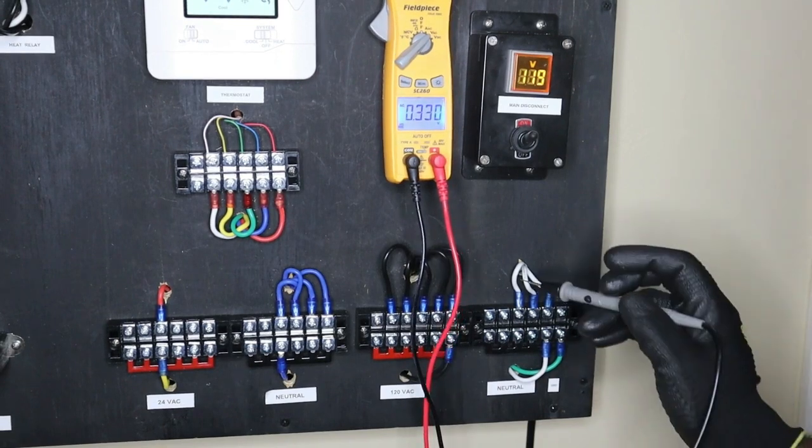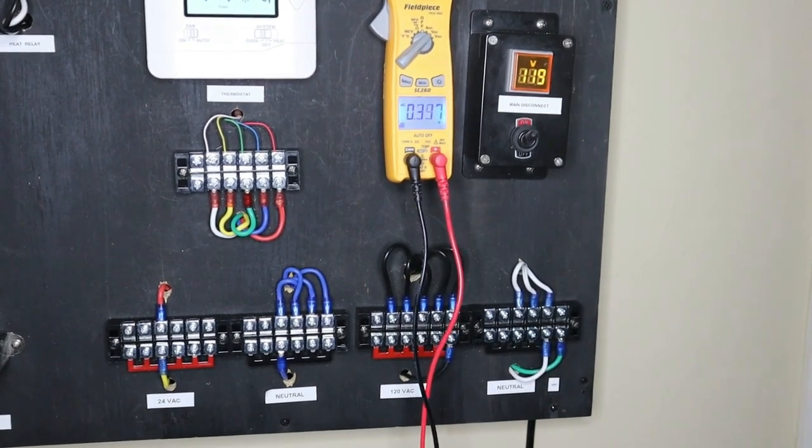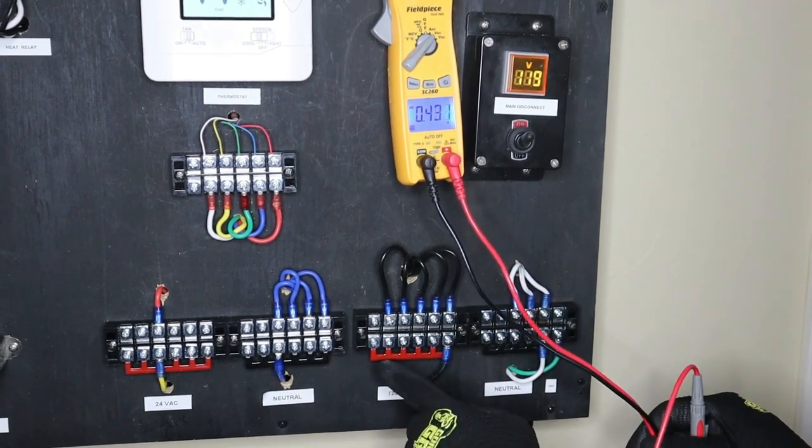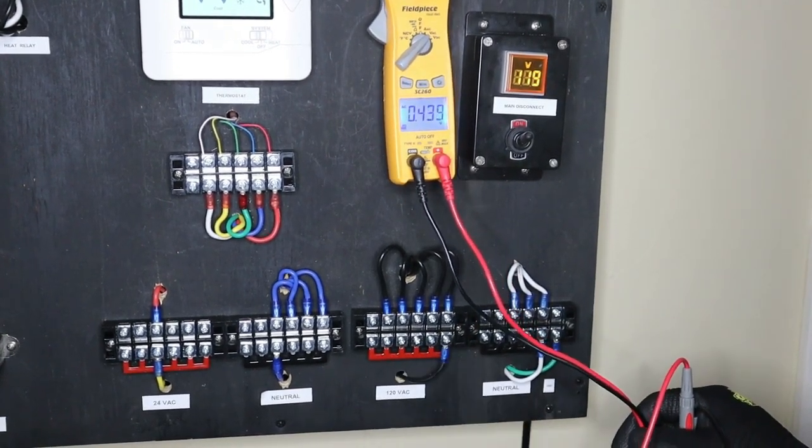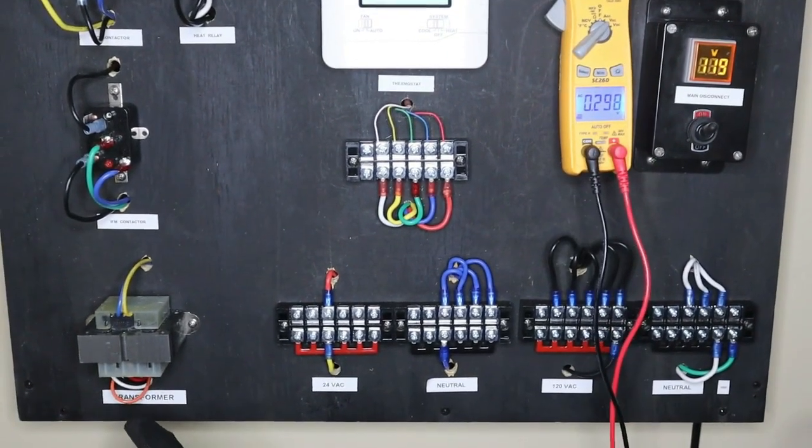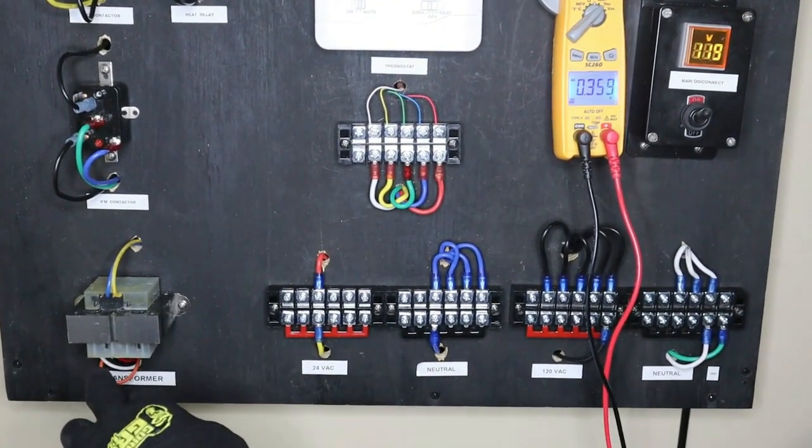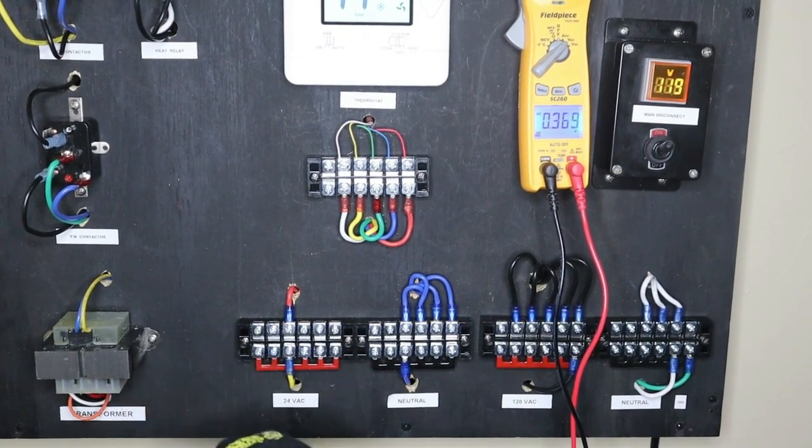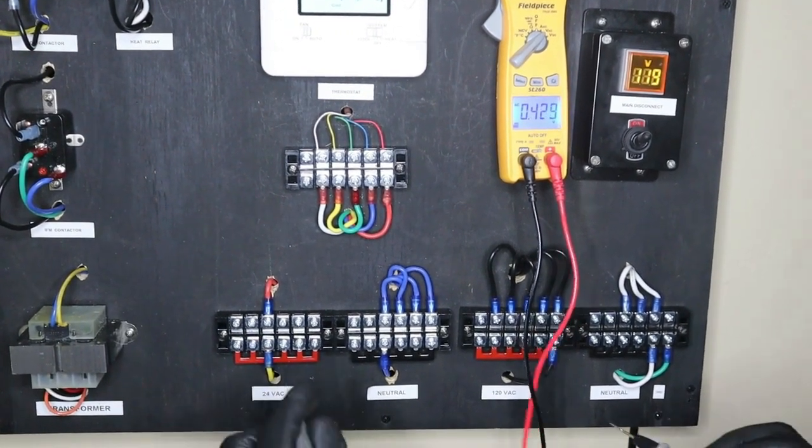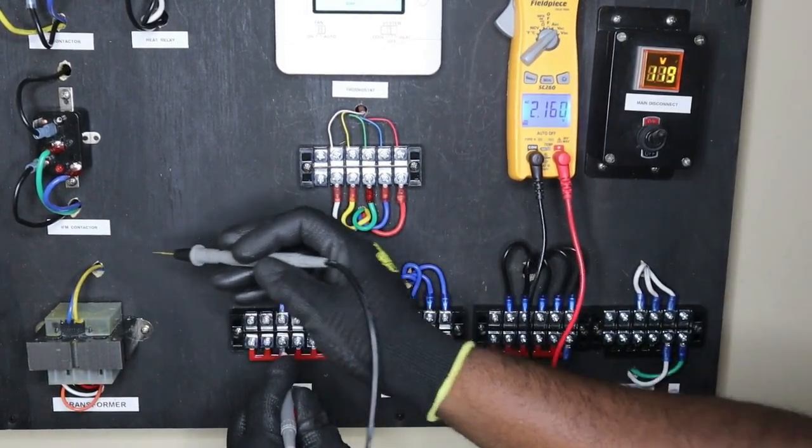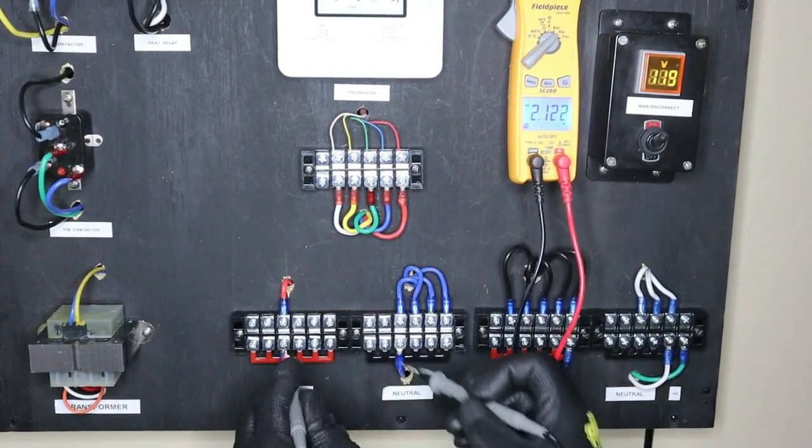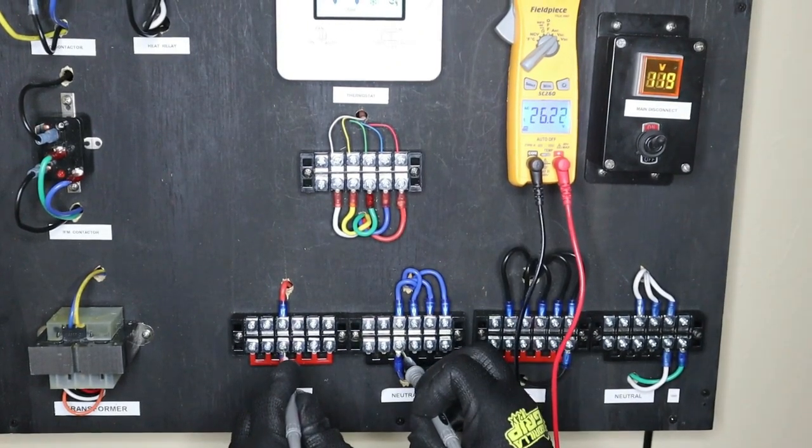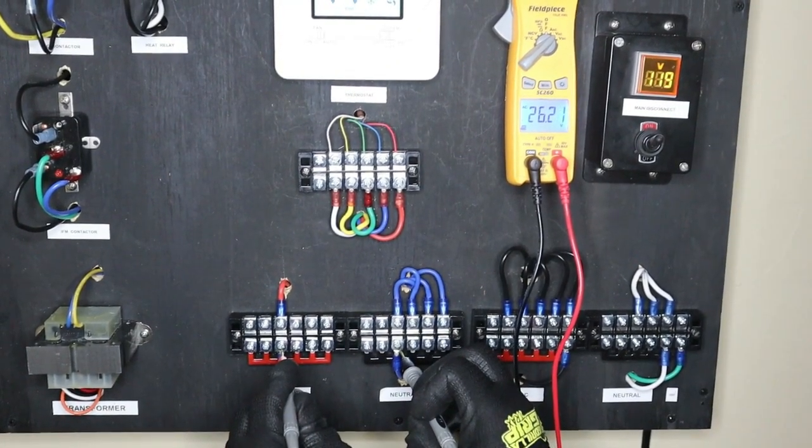Now when that 120 volts comes in one leg from my terminal block, and as you can see they're all jumpered, feeds to my transformer. My transformer then steps down the 120 volts to a low voltage 24 volts AC. So if I should measure here which is my yellow coming from my transformer and my blue coming from my transformer I have 26 volts AC.